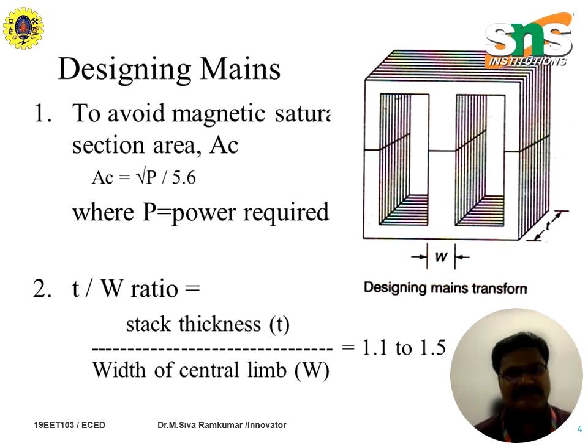Depending on the thickness-to-width ratio, we have the stack thickness over the center limb width. This should be between 1.1 to 1.5 to ensure structural and magnetic efficiency. So, two steps to remember: calculate AC for magnetic safety and ensure a proper T over W ratio.